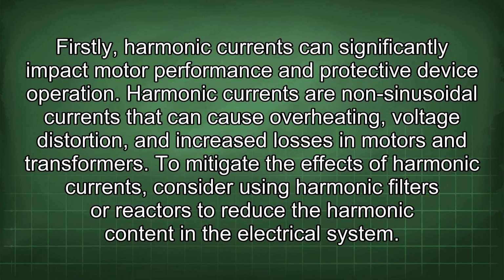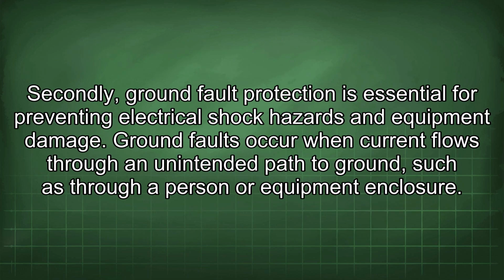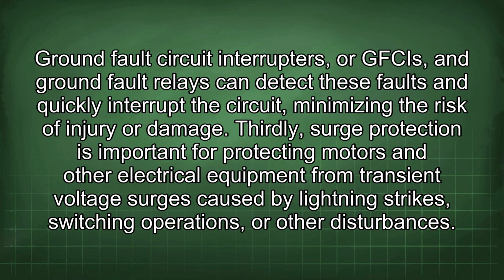Secondly, ground fault protection is essential for preventing electrical shock hazards and equipment damage. Ground faults occur when current flows through an unintended path to ground, such as through a person or equipment enclosure. Ground fault circuit interrupters, or GFCIs, and ground fault relays can detect these faults and quickly interrupt the circuit, minimizing the risk of injury or damage.